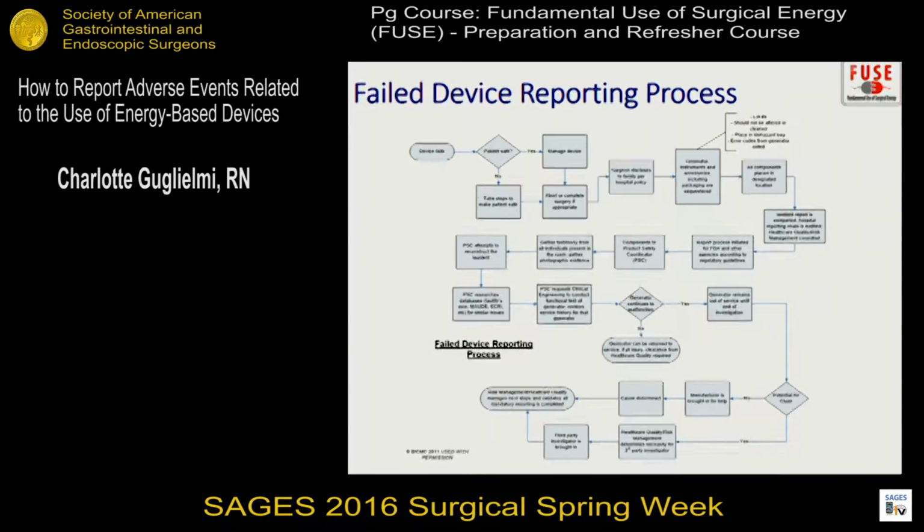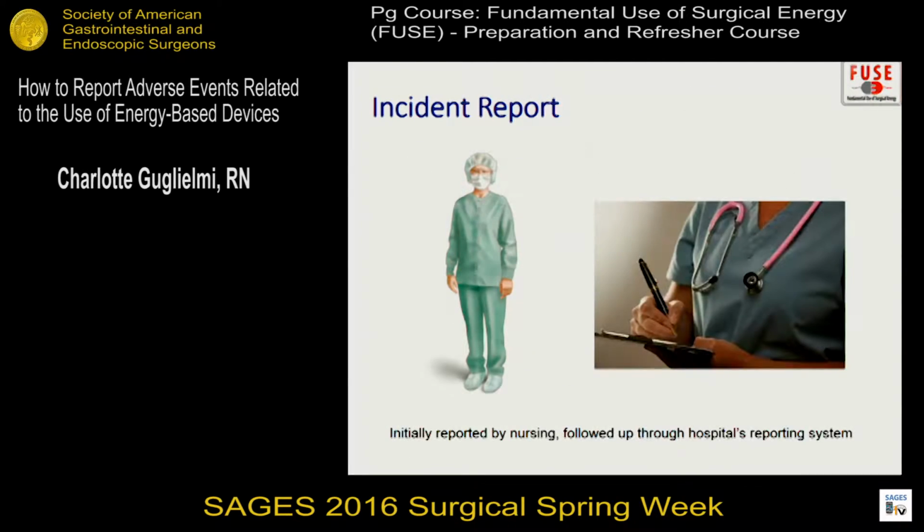We go through, and you want to be sure you sequester everything. Even if you think it wasn't involved, if it was drapes, if it was clothing that was on the patient, everything needs to be sequestered along with the generator, if it's an electrosurgical generator, and all of the equipment. They need to go to people who are going to try to recreate the incident after everything is taken care of. Again, we can provide this tool to you if you want.